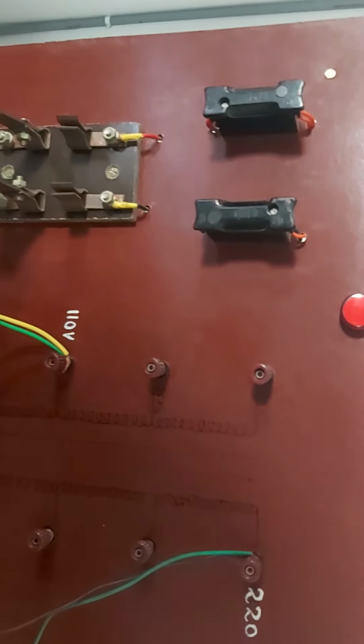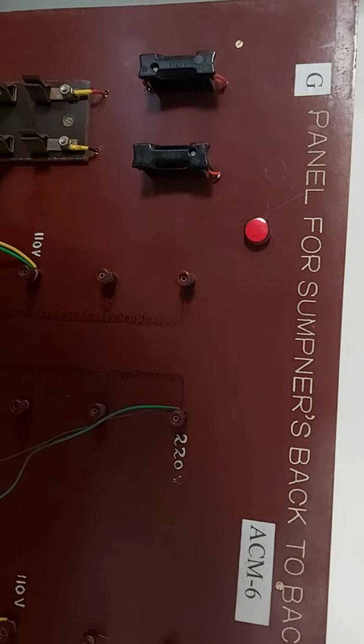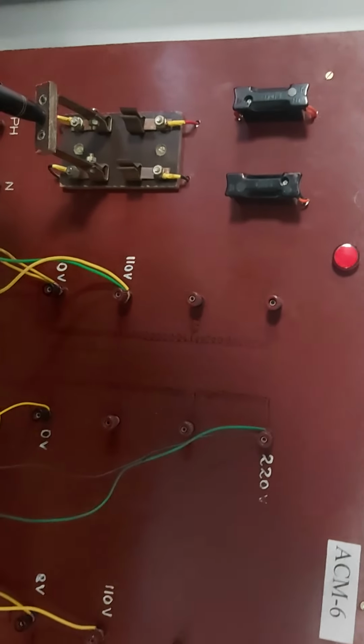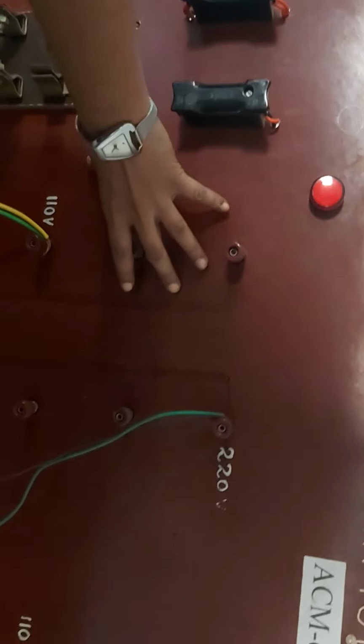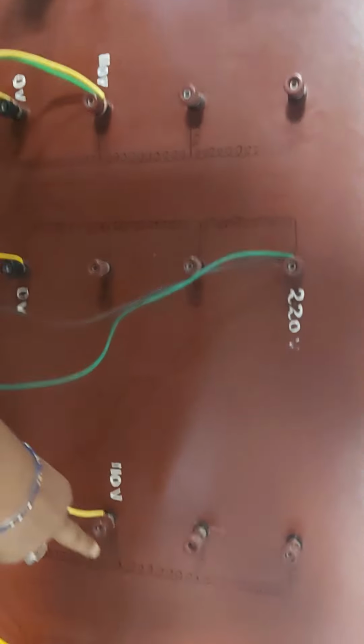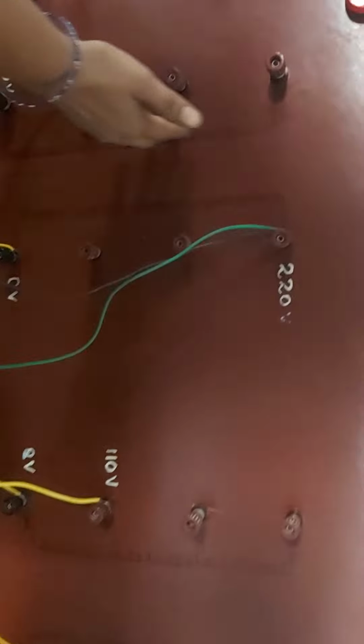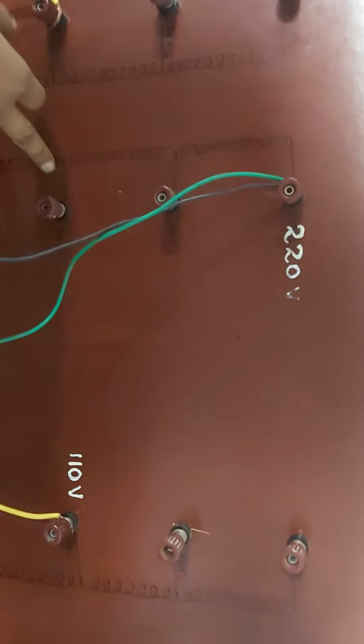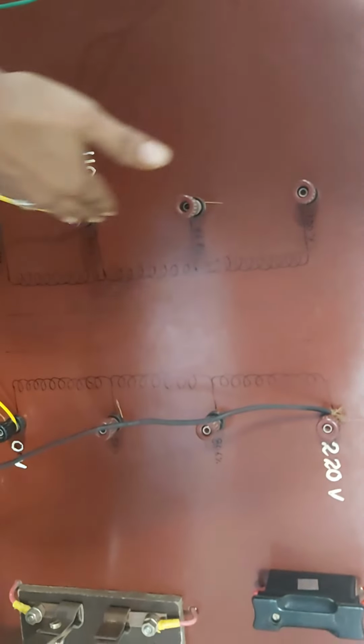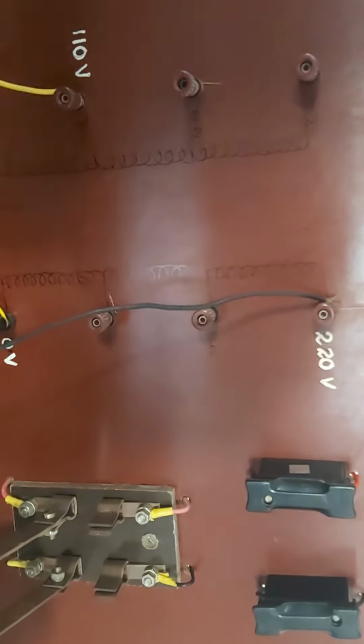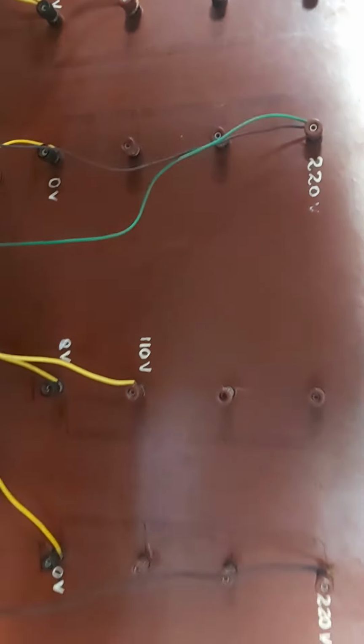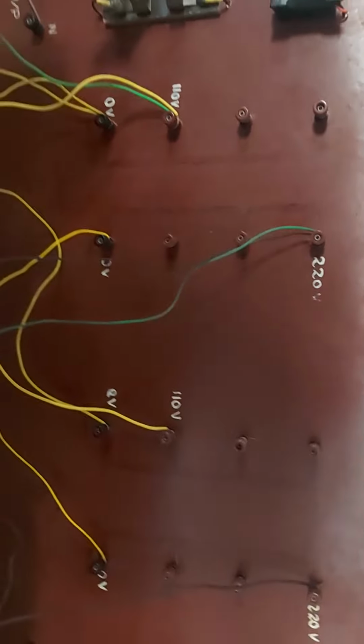This panel belongs to Sumpner's test, which is also called the back to back test on single phase transformers. Coming to the panel board, this is transformer 1 and this is transformer 2. Transformer 1 consists of a primary and a secondary, and transformer 2 also has a primary winding and a secondary side. According to the circuit diagram, we have to make the connections as shown.